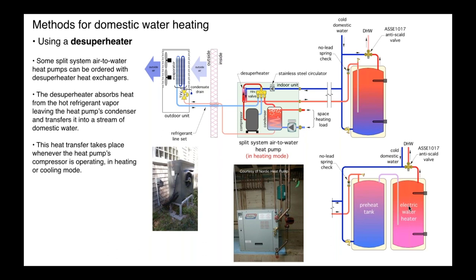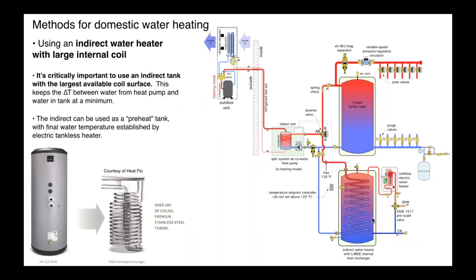I'm not sure if there actually is any research that's been published on this, what the performance gain would be. In theory, yes, you'd get more BTUs because the preheat tank would allow the water going into the de-superheater to be at a lower temperature and hence better heat transfer. Is it worth the price of the extra tank plus the higher standby losses? That would all have to be factored in. But it is an option I wanted to show, that is, again, sometimes used in the geo market and really is just as applicable to a de-superheater on an air-to-water heat pump.